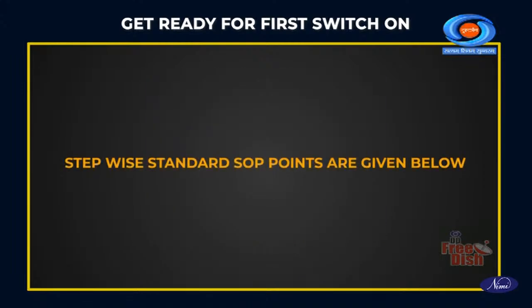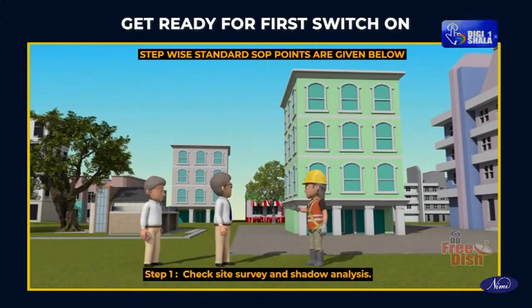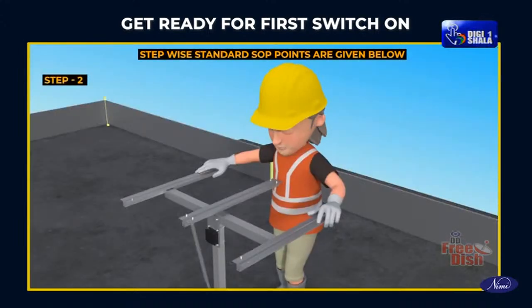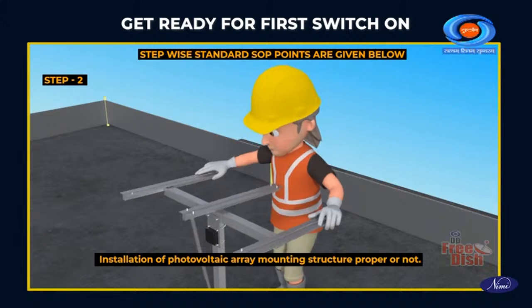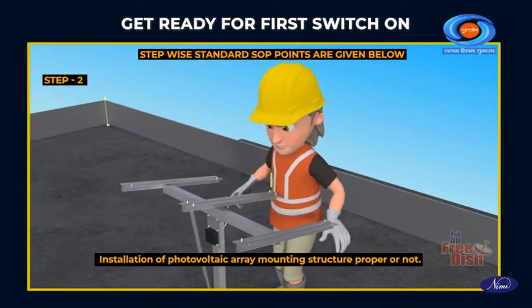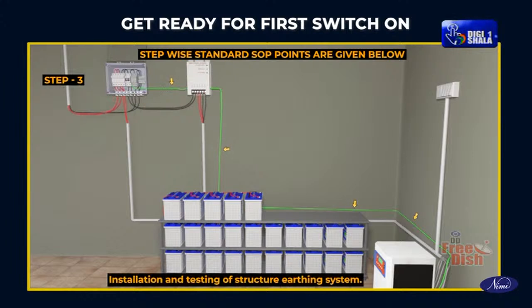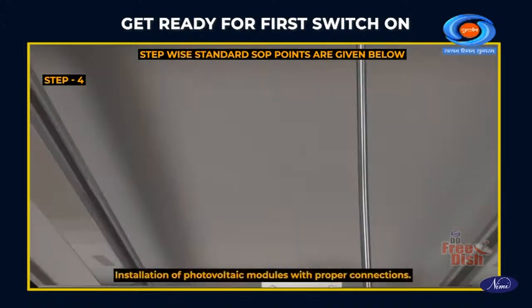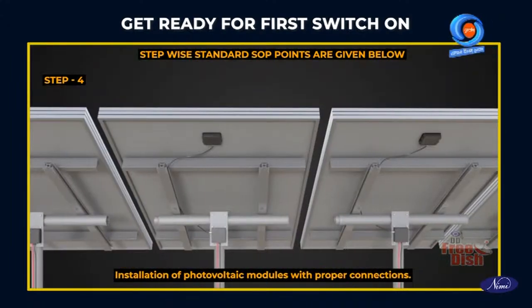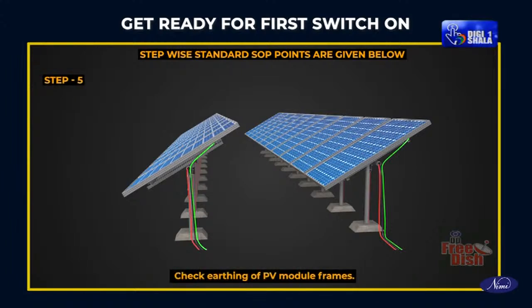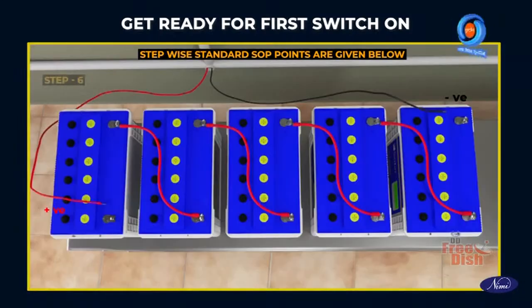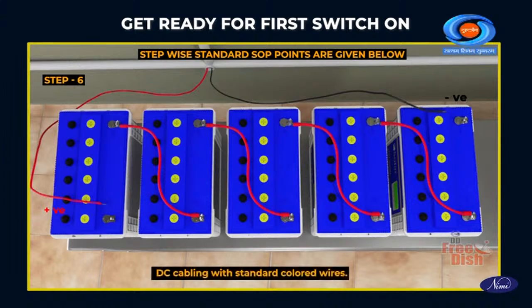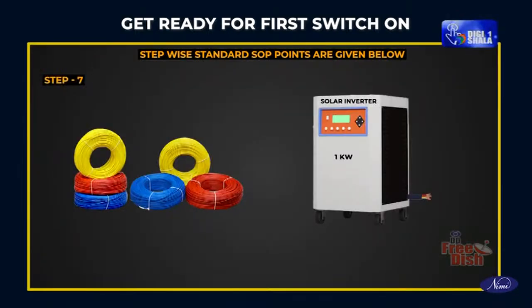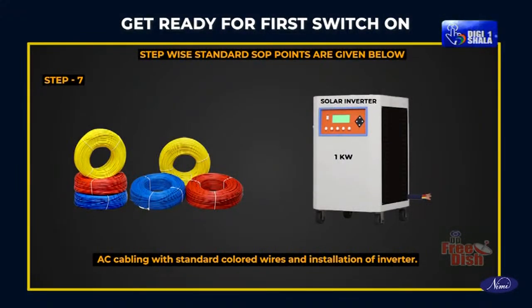Stepwise standard SOP points are given below. Step 1. Check site survey and shadow analysis. Step 2. Installation of photovoltaic array mounting structure proper or not. Step 3. Installation and testing of structure earthing system. Step 4. Installation of photovoltaic modules with proper connections. Step 5. Check earthing of PV module frames. Step 6. DC cabling with standard colored wires. Step 7. AC cabling with standard colored wires and installation of inverter.